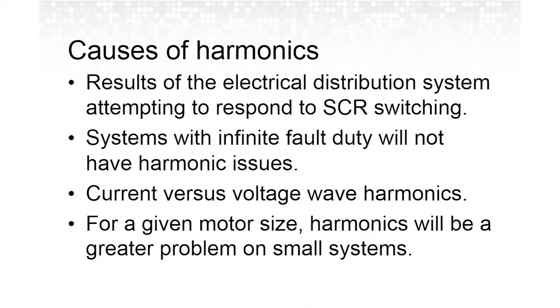Yeah, thank you, John. The actual cause of harmonics results from the electrical distribution system attempting to respond to the square wave from the SCR switching as they turn on and off to modulate the wave going to the motor. Since it has impedance, it can't respond instantaneously, and so you get harmonics created. If you had a system that had an infinite fault duty, which doesn't exist, but if you had one, you wouldn't see any harmonics.